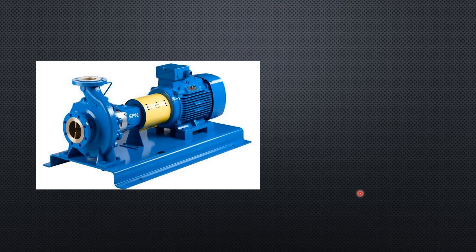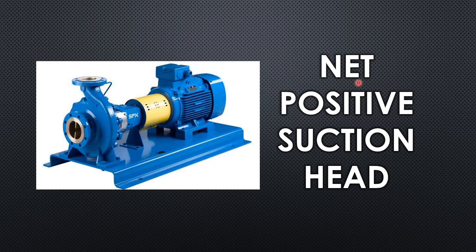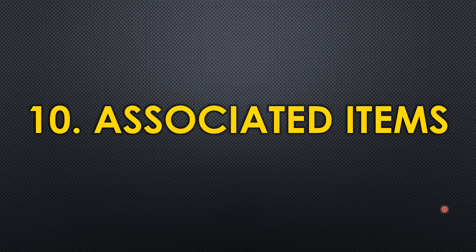The ninth parameter is NPSH — Net Positive Suction Head. This is the minimum suction head required for a pump to operate without cavitation. Cavitation causes air bubbles to enter the impeller, damaging the impeller surface and, over time, causing severe material damage. There are two values: Required NPSH and Available NPSH. You must maintain at least the Required NPSH as a minimum to ensure safe pump piping design.